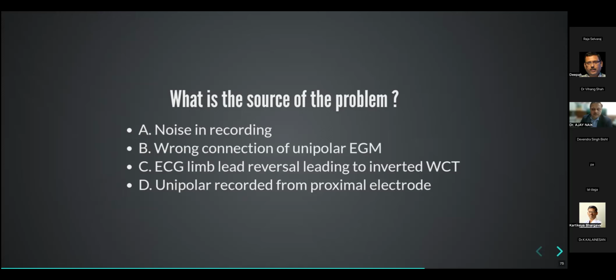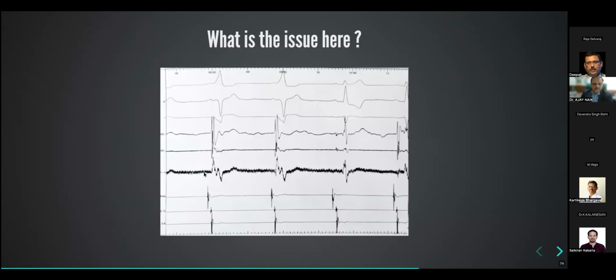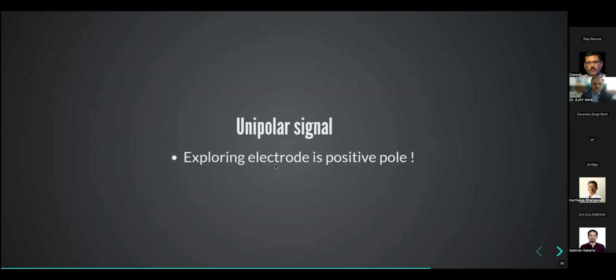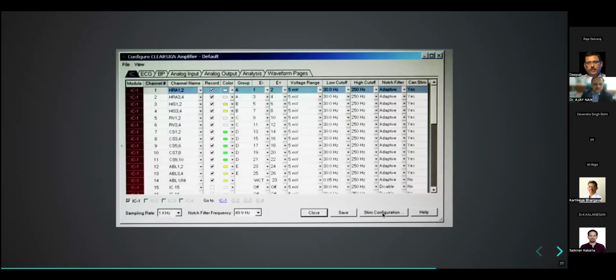Wilson central terminal is formed from all the limb leads. So the diagnosis here is that the unipolar looks inverted, and this means the connections have been made inverted in the amplifier. This is sometimes missed: the exploring electrode should be placed as the positive pole. So if we come back to this setup here, we have a unipolar, and in unipolar, this negative has to be set as the reference and positive has to be set as the exploring electrode. If you set this up the other way, your unipolar will look positive when you really want it to be negative. So just remember to do this.